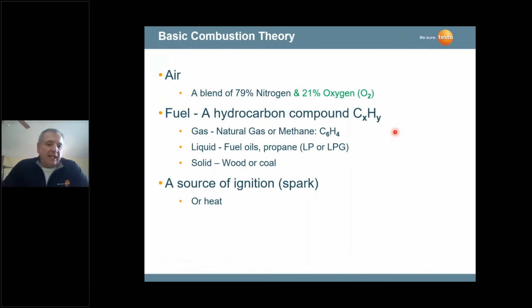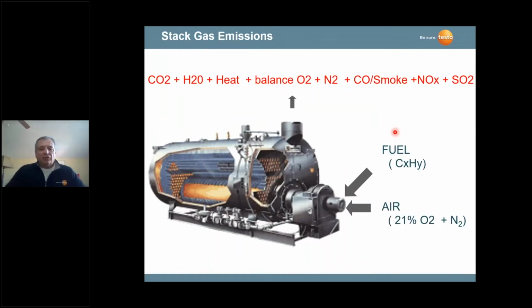In a burner, whether it's a residential appliance or a boiler, we're doing the same thing. We're bringing in air, which happens to be 21% oxygen. And just like our bodies, we use the oxygen. The oxygen in a burner is used to create the combustion process. It's very critical that we maintain the correct amount of air or oxygen going through the burner so that we have complete combustion. Fuel, I know you guys have a lot of gas up there. I know you guys have a lot of fuel oil. And then also we talked about the source of ignition. So we're mixing fuel and air together, and air again, 21% oxygen.